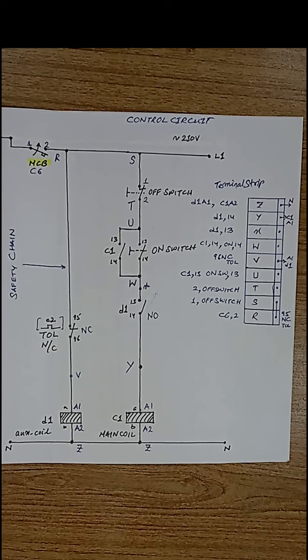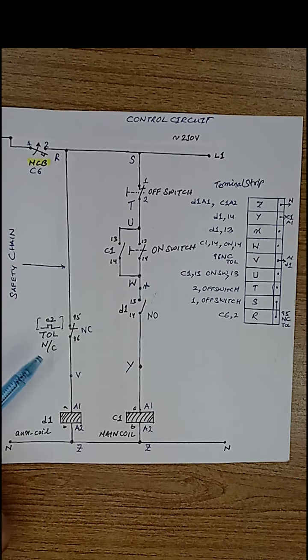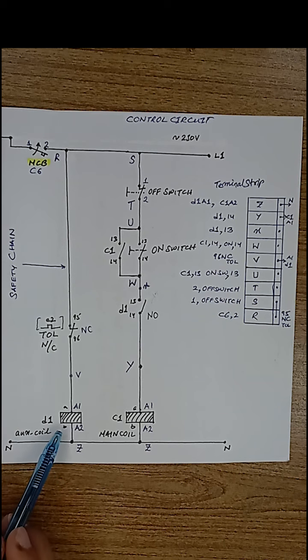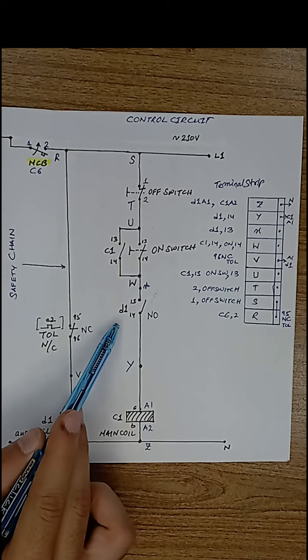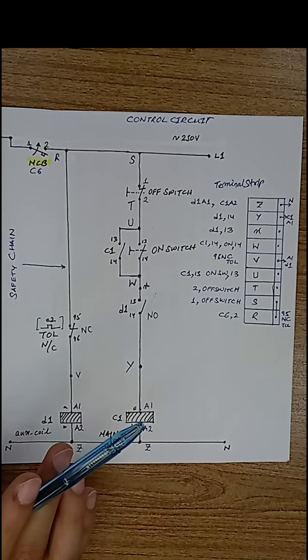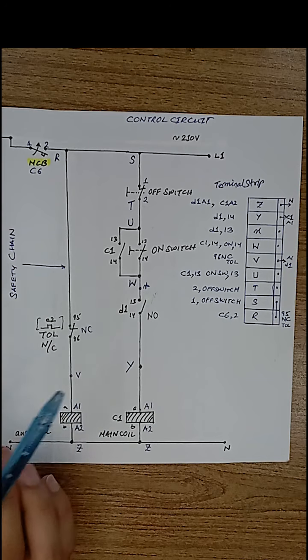This part of the single line diagram is the control circuit for the direct online starter. Once the control circuit MCB is closed, current will flow from the single phase source through the normally closed contact of the thermal overload relay and will energize the auxiliary contactor coil D1. As soon as the coil energizes, the normally open contact of the auxiliary contactor closes and the circuit is now ready to start with the push of the on button.